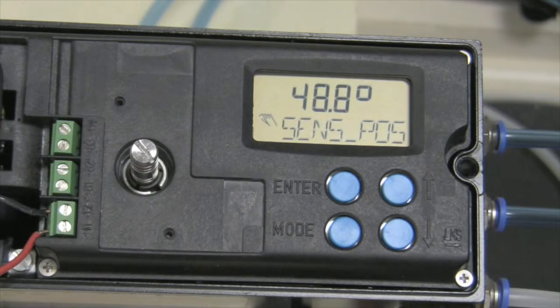Remember when we are calibrating the unit, we need to make sure that the sense position is between positive 57 and negative 57. We can see that this one is at positive 48.8.